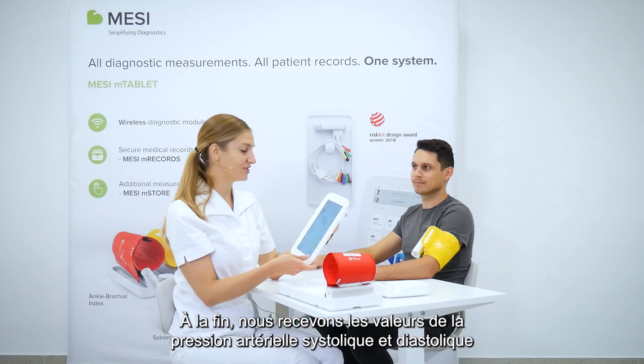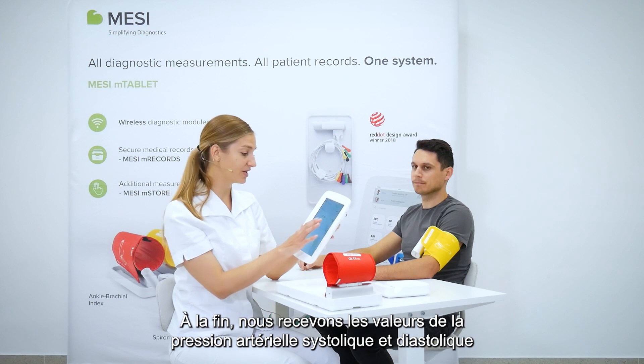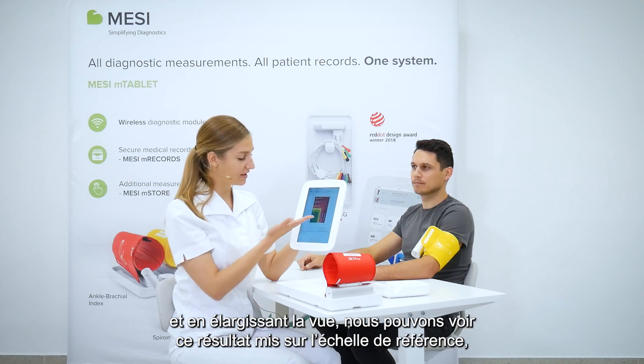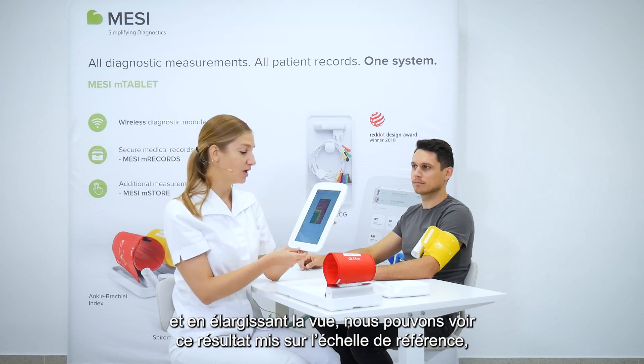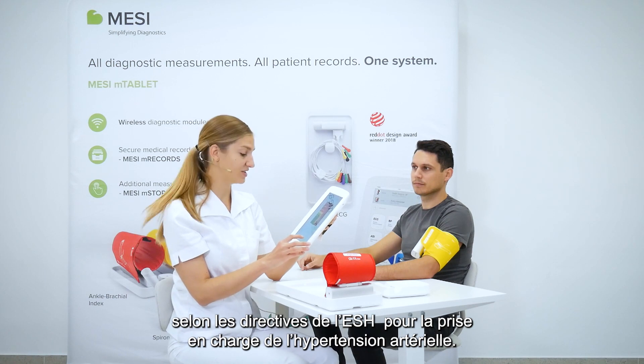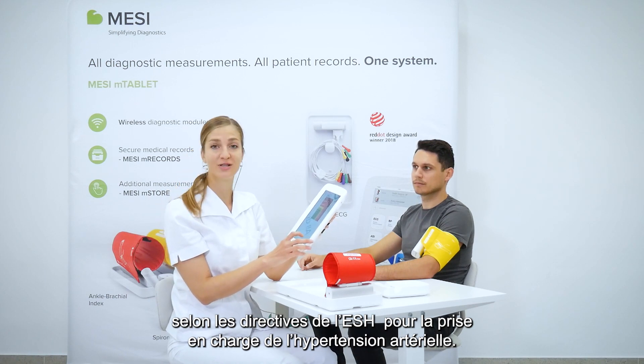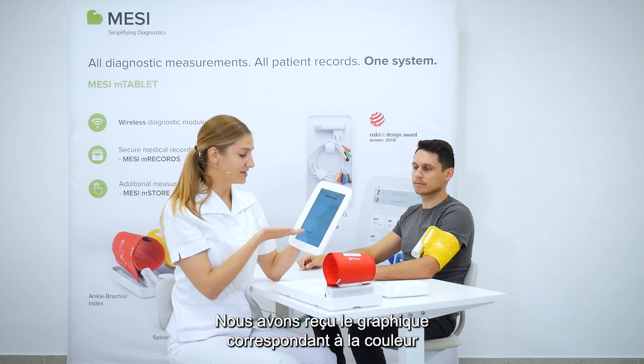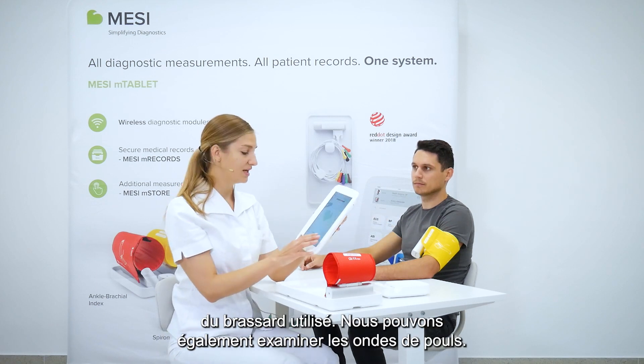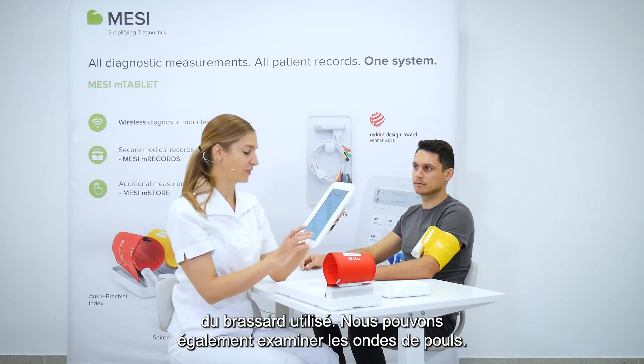In the end, we receive the patient's systolic and diastolic blood pressure, and if we expand the view, we can see this result placed onto the reference scale according to the European Society of Hypertension's guideline for management of arterial hypertension. We receive the graph which corresponds with the color of the cuff that we used, and we can also review the pulse waveforms.